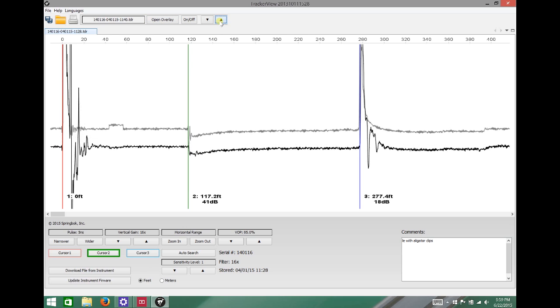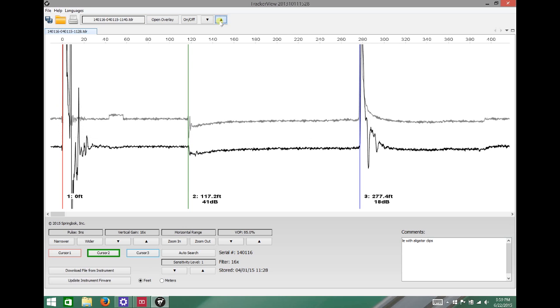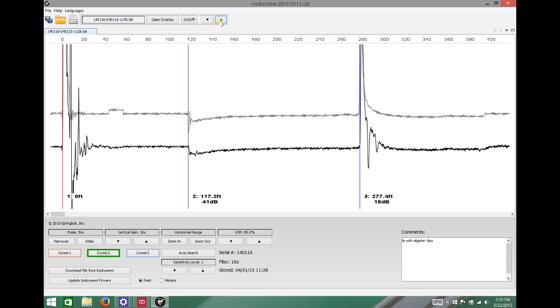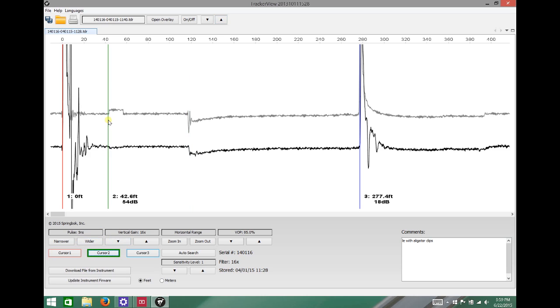The dark is the alligator clips and the lighter one which we're moving up to take a look at a little bit better is the shot using the probe. And right away we can see that there's a difference. It's a much cleaner waveform, much cleaner initial pulse and there's something going on at about 42 feet.